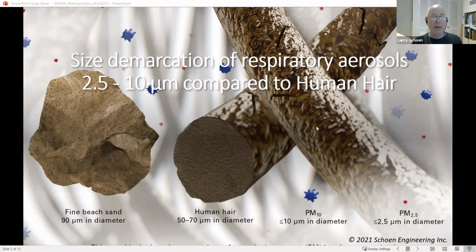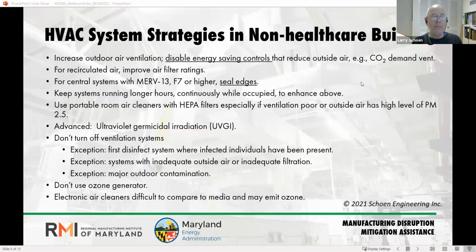That's the 2.5 micron. And let's take a look at the next slide now, which gets into the details of what we actually can do in the HVAC. What's underlined in the first bullet is that there are energy saving strategies, which are great to do when we're not in the midst of a pandemic. One of those strategies is to reduce the amount of outdoor air so we're not conditioning more of it than we need to. Now, in this beautiful weather we're having at this time of year, this is less of an issue. But as we get into those hot, humid days of summer, outside air that you bring in does require cooling and dehumidification. And so generally, when we're not in the midst of a pandemic, we want to reduce that to save energy.